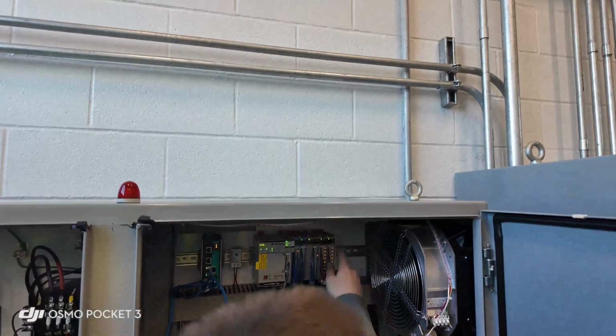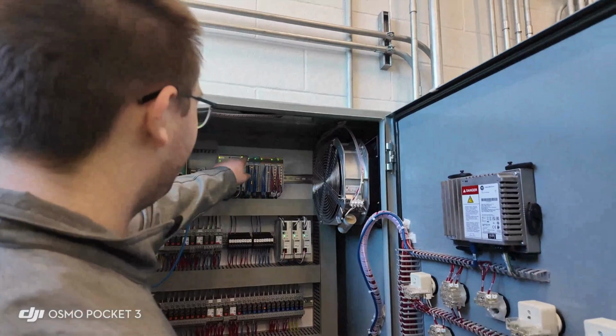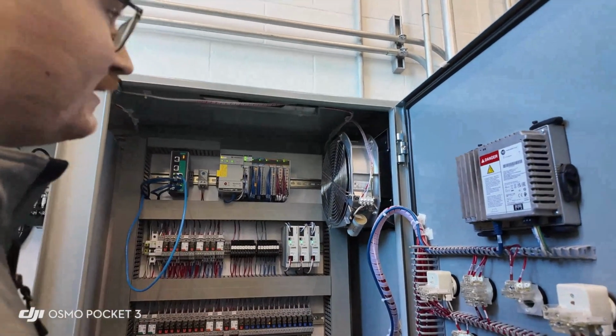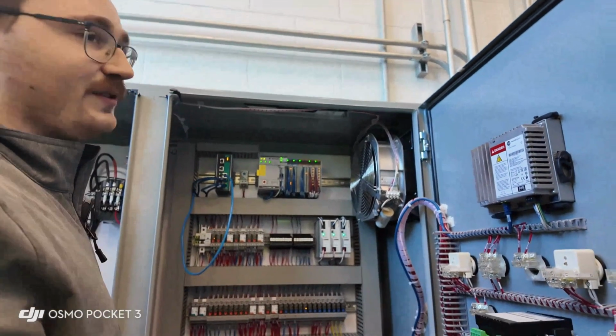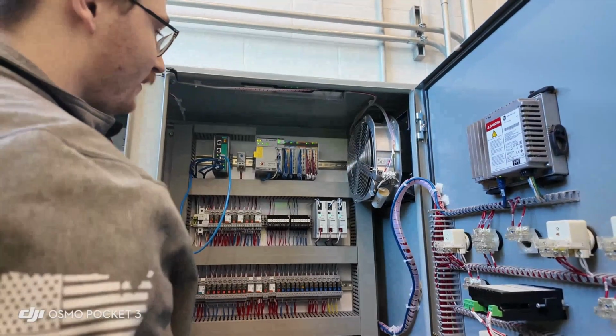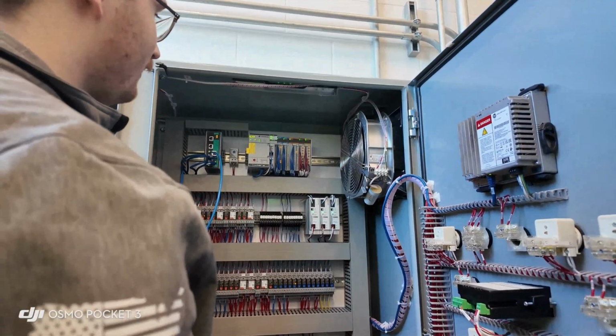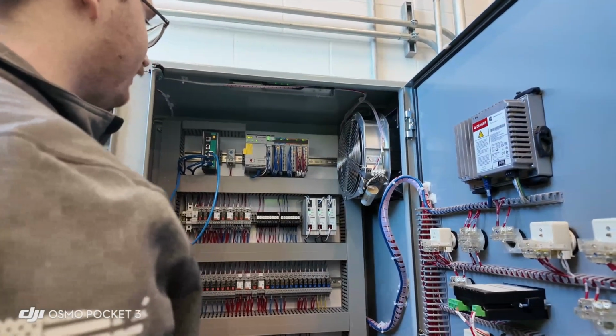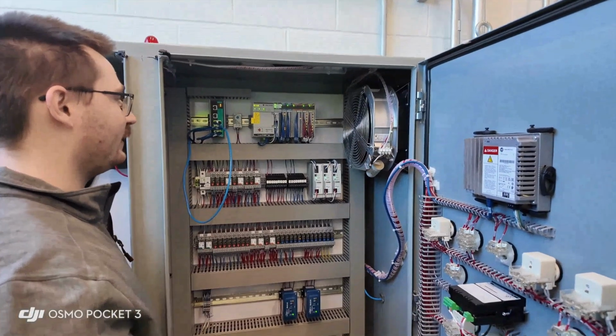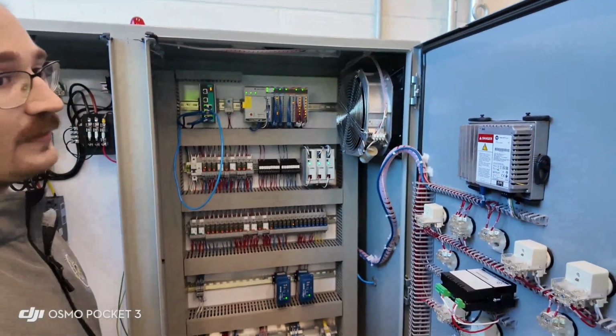You want to see lights up here, it means the module's powered up. It has mod power and SA power. So if you ever see any of those lights out, it's a pretty big concern because there's some sort of power issue going on inside the controller. So that's something to monitor. There is a signal, PLC fail. If the PLC does fail, you should be able to get that alarm to SCADA.